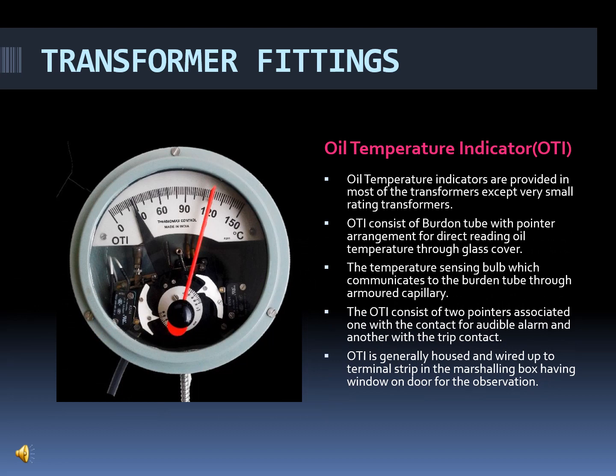Now we will move on to another fitting that is called the oil temperature indicator. In short we can call it OTI. Oil temperature indicators are provided in almost all transformers except the very small rating transformers. In our transformer, which is a 2 MVA transformer, it is provided with the oil temperature indicator. The oil temperature indicator consists of a Bourdon tube with a pointer arrangement for a direct reading of oil temperature through the glass cover. I have enclosed the image. You can see it is a Bourdon tube with a pointer arrangement, and the reading of the oil can be done directly, visible through the glass cover.